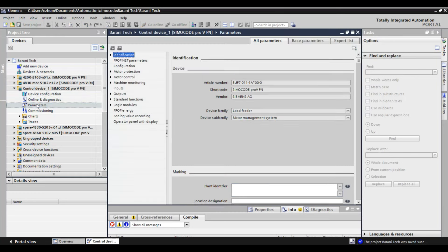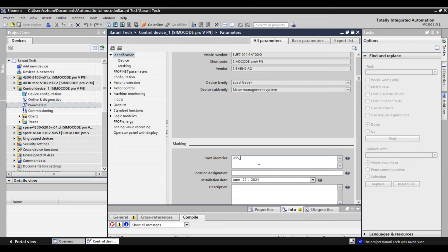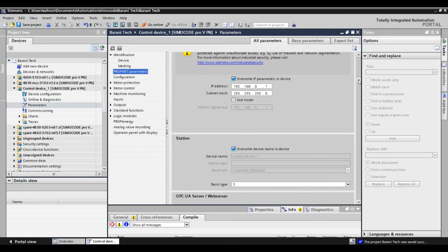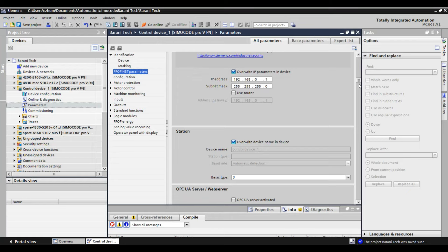First I am going to give a name for this feeder. For example, I am giving the name 'LNA540XX dosing pump,' but we have to use the actual feeder and tag number for easy identification. Next, I am going for PROFINET settings. If the SIMOCODE is connected with PROFINET, then we have to give the name correctly — the PROFINET name which is given by the DCS engineer or handed over to you. Click on 'PROFINET Parameter' then scroll down to 'Station.' This device name is the PROFINET name. When you click on overwriting, the device name and the name of the template will be matched automatically, so if we change the template name, the PROFINET name also gets changed.